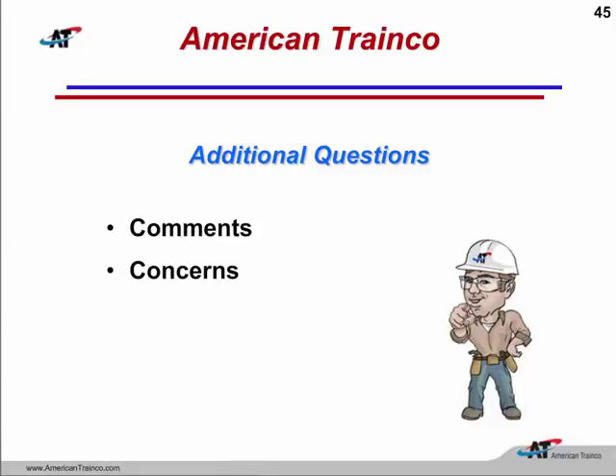And we do have several questions in queue, Bob, so I'll just jump to the very first one here. Our first question is, I have a question about the elimination of Category 0 for a cabinet panel that was a Cat 0 with an arc boundary of 9 inches, for example. Is it now no PPE required, or is it a Category 1? That's a great question. With the analysis method, it is going to be a PPE Category 1.